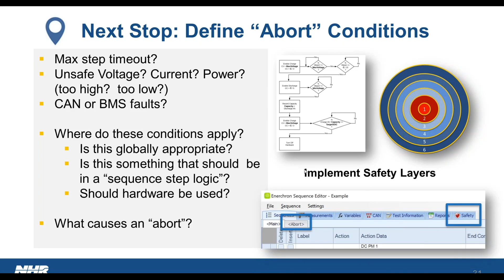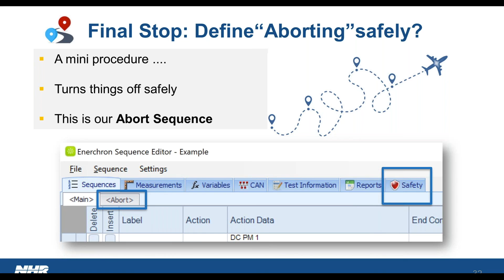And then finally, we need to define what it means to stop safely. So from any test or any step inside the sequence, if I'm running that step, what would I want to do to make sure the test ends safely? I might not just want to turn off the cycler—I might want to first change the temperature chamber, adjust current levels, or open up a relay. The sequence of events that allows the system to shut down safely is another process, and it goes inside the abort sequence.